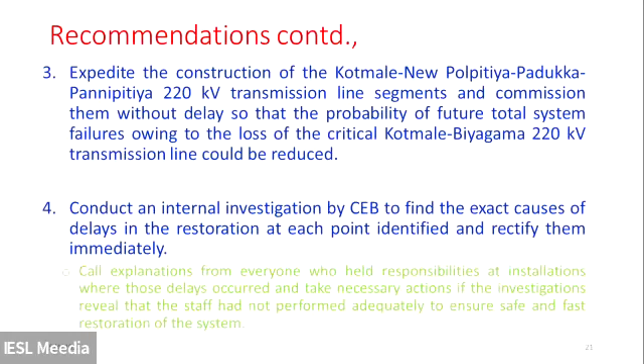In the restoration, though I said that the system control managed to restore the network back in 5 hours and 15 minutes, we could observe there were mainly 9 points where there were delays. For example, in Kothmale, if I remember correctly, the delay was around 2 hours. There was a pressure relief valve operation, and then fault alarms coming, some error message coming, which was not displayed to the operator, and so on and so forth. There were several incidents like that on both circuits 1 and 2, and also in Samanalawa there was a delay, and then in the New Lakshapana there was a delay. Likewise, there were 9 delays, and these were the identified ones. We would like the CEB to look into that.